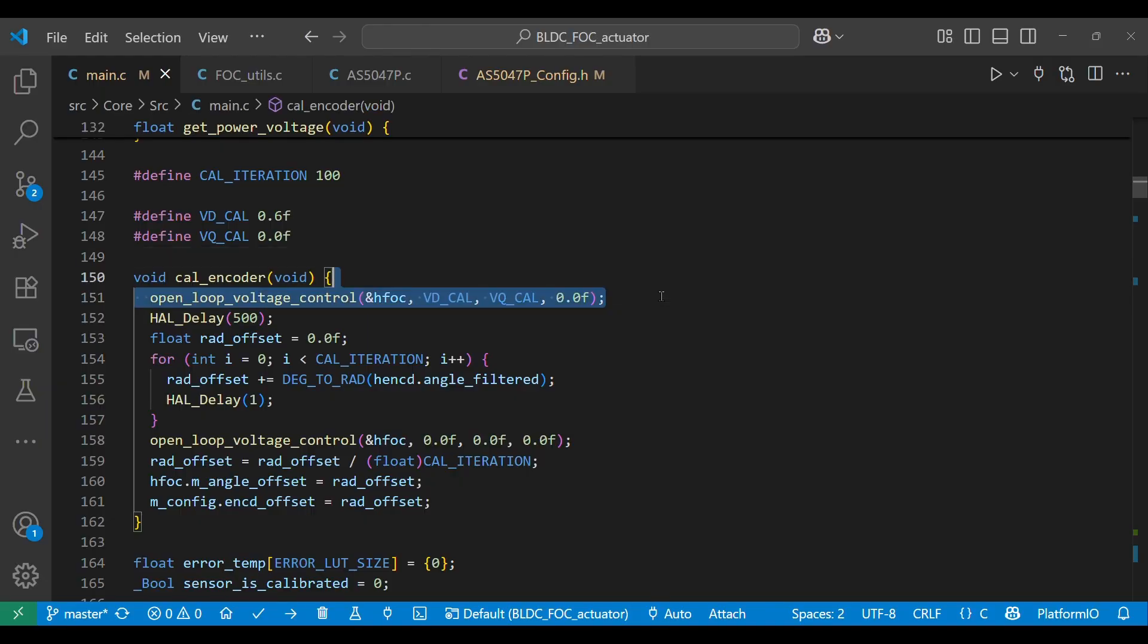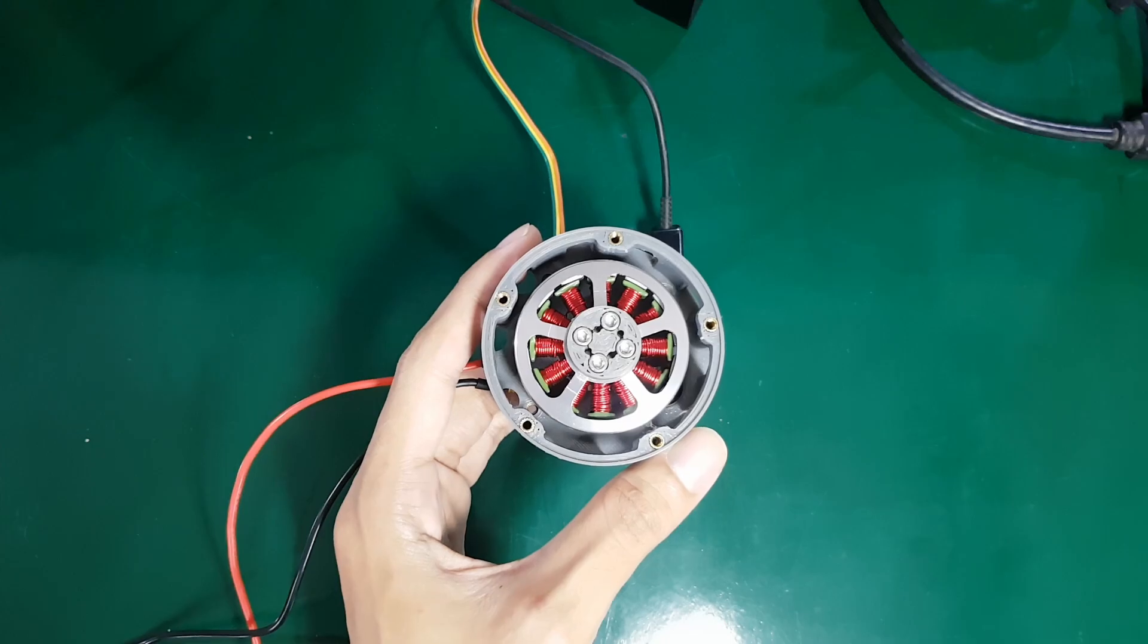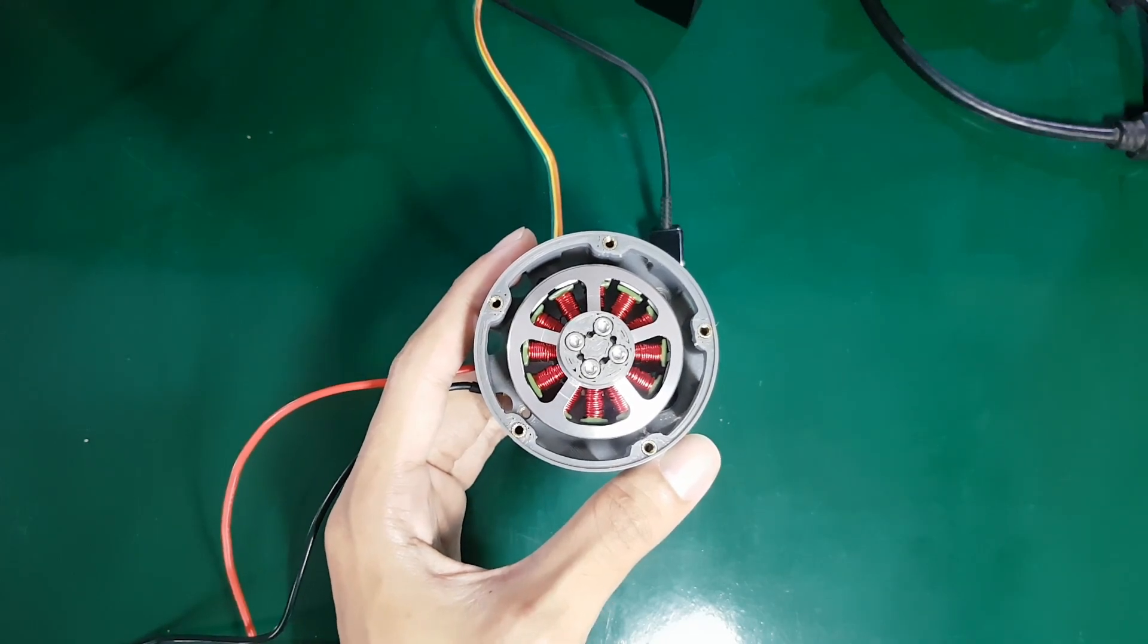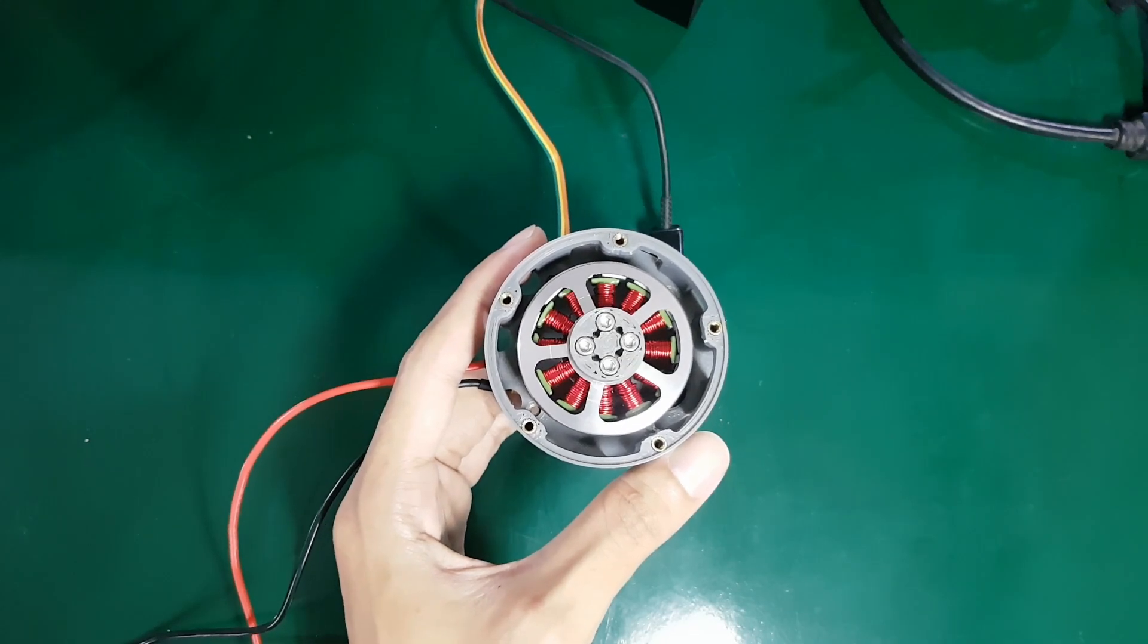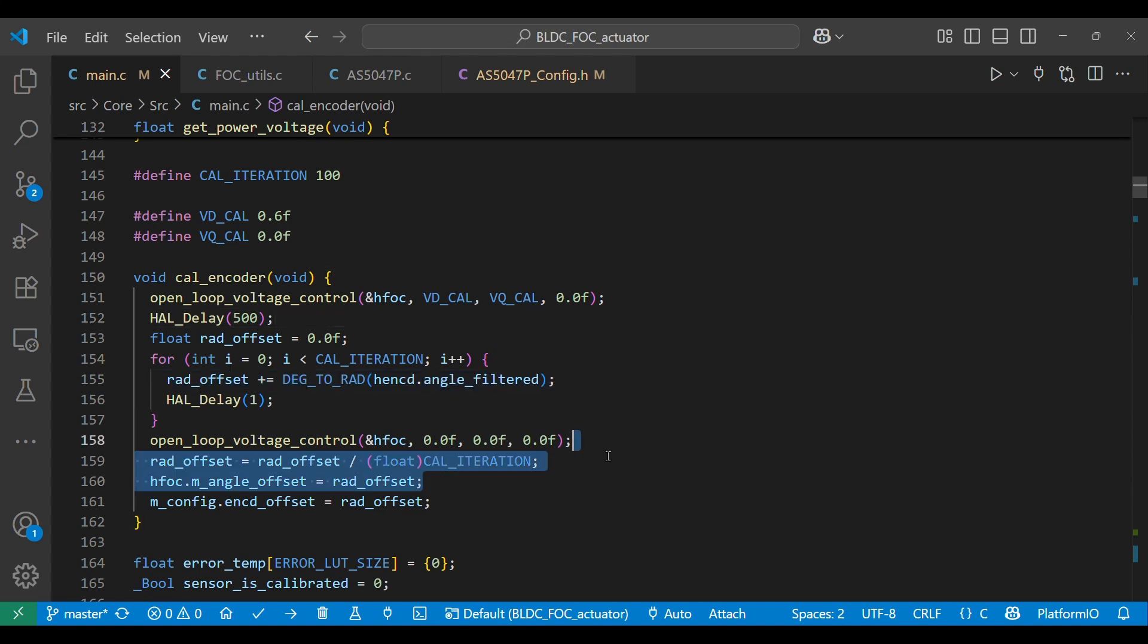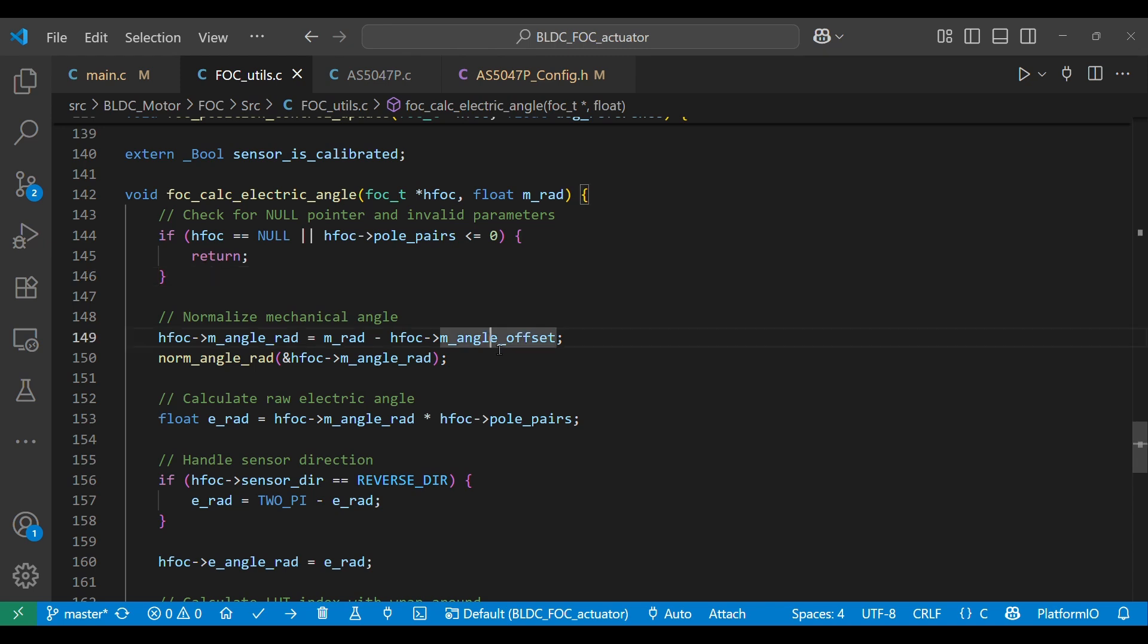First, apply a direct voltage VD and an electrical angle position of zero degrees. Second, when the rotor's magnetic field is locked in this position, read the encoder's angle value. Third, use this value as the offset and subtract it from each encoder reading to obtain the actual rotor angle.